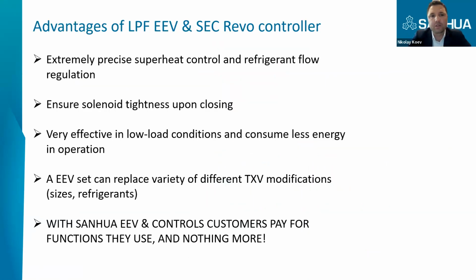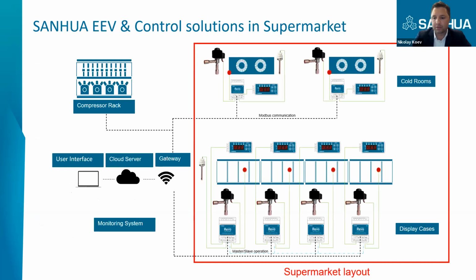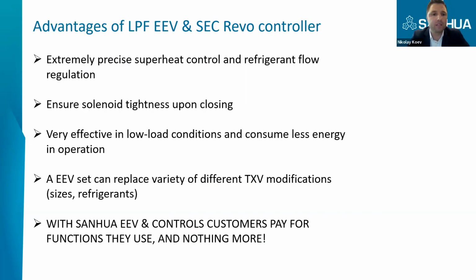And to summarize, what are the advantages of using our electronic expansion valve and our SEC Revo controller? It provides an extremely precise superheat control and refrigerant flow regulation, which of course results in much better energy efficiency. With our electronic expansion valves, there is no need to use solenoid valves because we have a soft sealing design and the tightness is similar to a solenoid valve. These electronic expansion valves can work at a very low load, very effectively. And you may know that stepper motor electronic expansion valves consume less energy in operation compared to pulse width modulation valves.